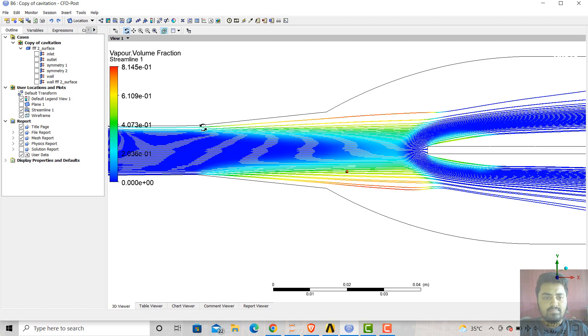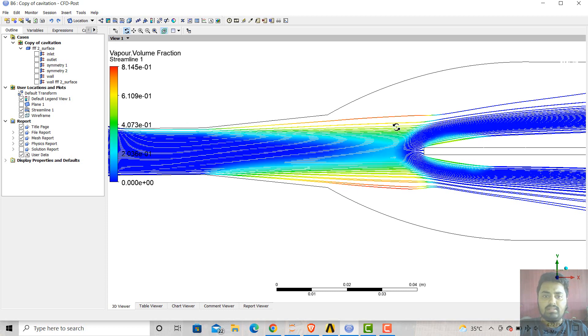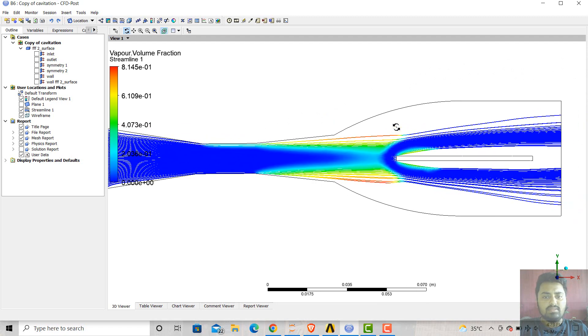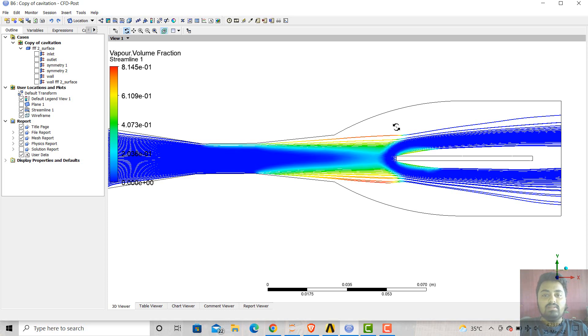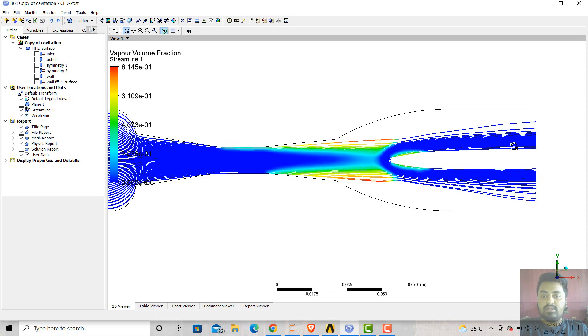Here, these are the bubbles. These bubbles are formed due to pressure difference. If we consider the pressure at any point, and if that pressure is less than or equal to the vapor pressure, then the vaporization process takes place. And when the vaporization process takes place, due to this heavy pressure difference, the bubbles are forming. These bubbles are continuously carried out by the flowing liquid.